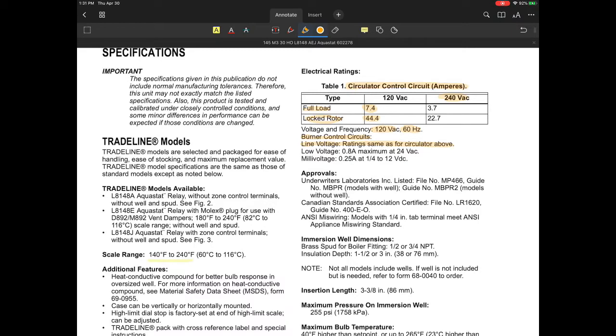That's normally the case. A lot of times people might put in an extra or additional relay, a circulator relay or a burner circuit relay, that will be auxiliary to this. What they're not telling us in here specifically, but we'll see it later, is that there's a completely separate circuit pole for the burner circuit as well as the circulator. In other words, there's a completely separate set of relay contacts for the burner circuit as well as the circulator. So this one might be the burner, this one might be the circulator, and my point is that the ampacities would logically be the same in a lot of these cases to provide you the operation of that. Anyways, that's a little bit on that. The low voltage circuit, they're listing as 0.8 amps maximum.